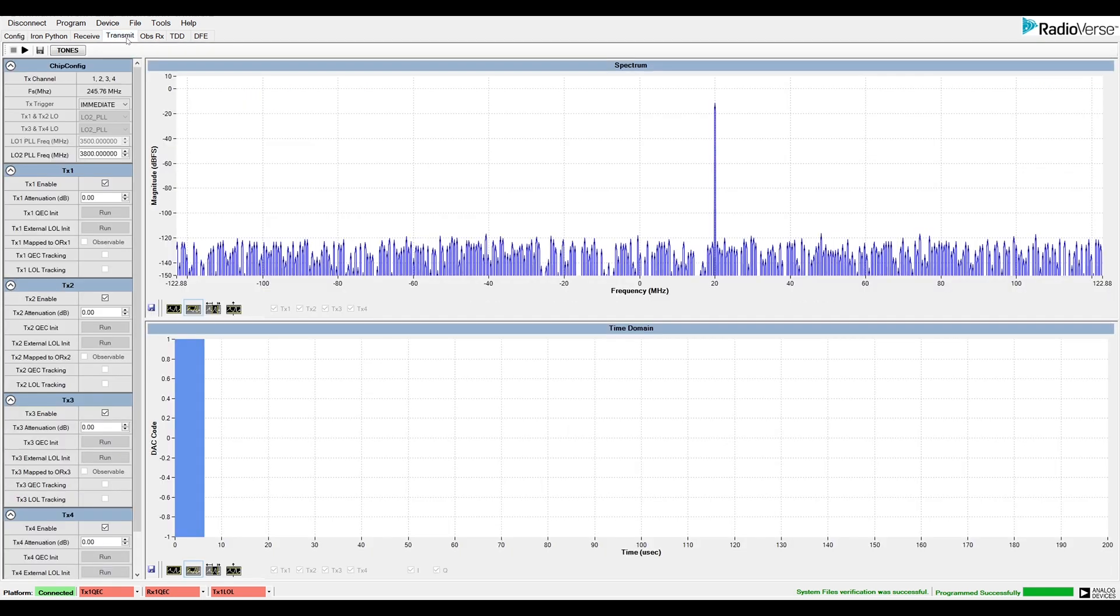Now, we can move to the Transmit Data tab. This tab can be used to generate CW tones, load data vectors, control TX attenuation, or run further initial calibrations.